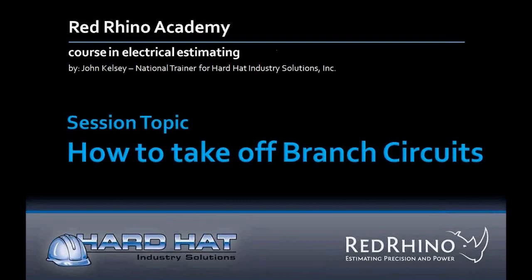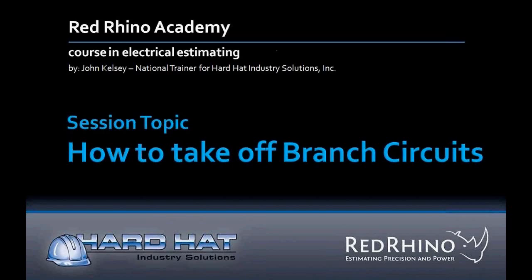There's a difference between doing branch circuit material takeoff and feeders takeoff. By definition, branch circuits use conduit which is one inch or smaller, whereas feeder conduit uses conduits size inch and a quarter and larger. Using Red Rhino estimating software, the real time saving feature is that you can enter multiple conduit runs all at the same time. In this example, we'll take off and input several branch conduit runs simultaneously.